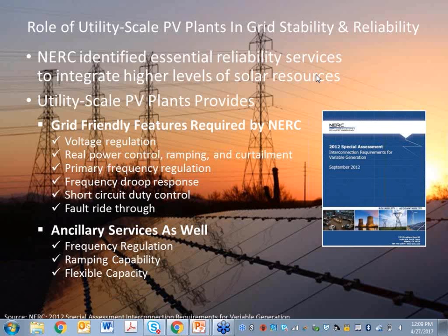Let's talk about AGC, for example. What's necessary, technically speaking, is the ability to receive an AGC signal from the CAISO system. Most of the utility scale plants we build have a CAISO rig, which is used to send data to CAISO from the plant and can also receive data in the other direction, which could be an AGC signal. The second aspect is then tying that AGC signal with the controller. These are all capabilities we're going to test out, and it's not rocket science to make that happen.